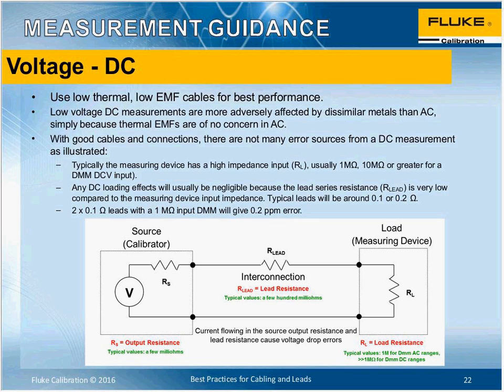Like Paul mentioned, DC measurements are more adversely affected by dissimilar metals than AC, simply because thermal EMFs are no concern in AC. With cables and connections, there are not many error sources from a DC measurement. And so if you have this diagram below, that's probably the simplest connection, and with the least amount of errors, just based on what DC is and how it's measured.